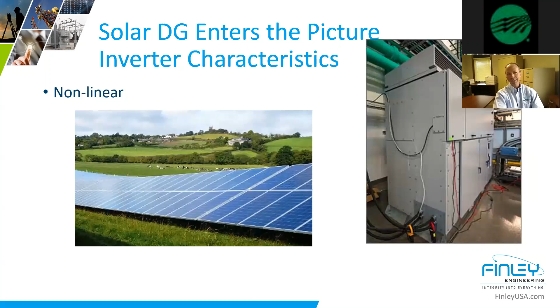I'm going to point out some standards here because it's instructive for the discussion. IEEE is taking the lead, and UL is the listing agency for coming up with the products and devices and certifying them. When we permit these systems coming on, we want to see their UL cert. What's interesting is if you look at the standards, the '03 standard for 1547 said they shall not actively regulate voltage and shall trip on abnormal voltage or frequency.